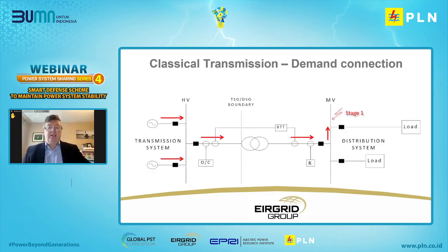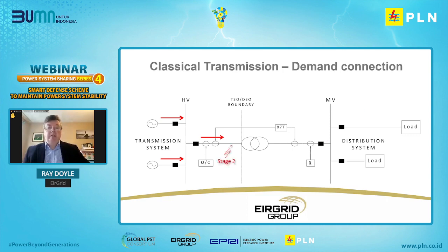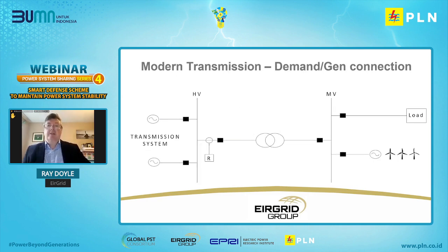Typically, you can see there on the HV side, we would have fitted overcurrent protection. Stage one would have dealt with the fault on the MV system. Next slide, please. The instantaneous stage two would have dealt with faults on the high voltage side of the transformer. Okay, so next slide, please. And go again, maybe.